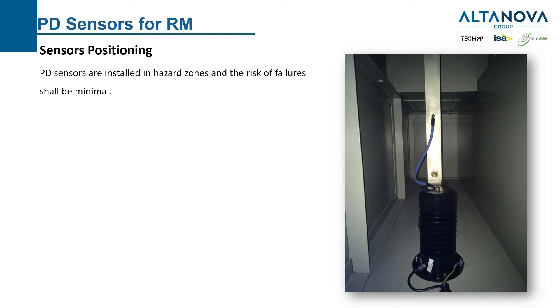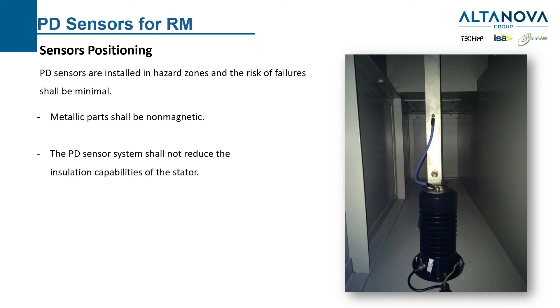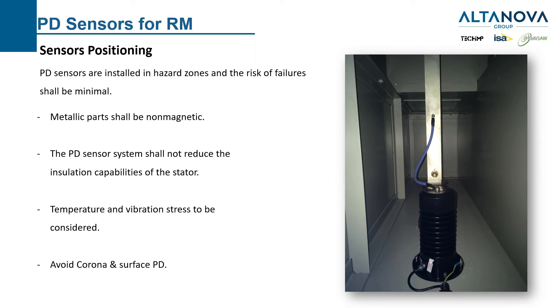Regarding sensor positioning, for the same reason — we install these sensors in a particular environment and normally only once in a lifetime — we have to make sure everything is done properly. The sensor shall not have magnetic bars; it should not reduce the insulation capabilities of the stator and bus bar section. Sensors must be acceptable under ongoing temperature and vibration stress, and very importantly, we must make a proper installation with proper spacing, avoiding corona and surface PD that would affect the PD measurement for the rotating machine.